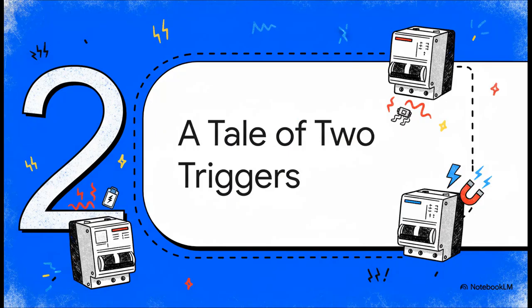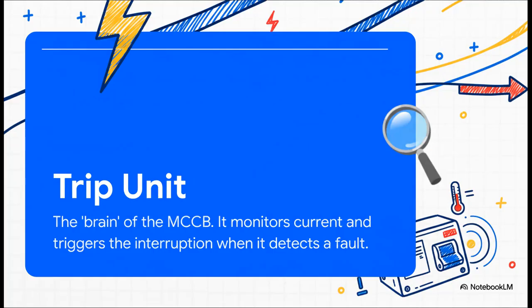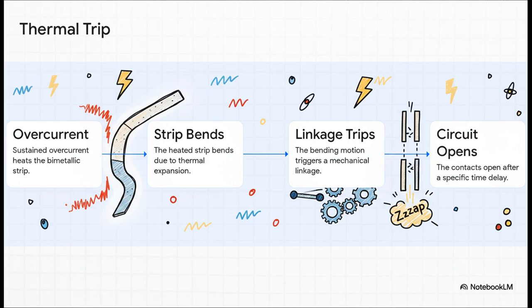Okay, so how does one little box pull off this dual protection mission? Well, it's not with one single mechanism. It's actually a really clever combo of two different systems working together. You could call it a tale of two triggers. But before we get to those triggers, we have to meet the command center, the trip unit. This is the brain of the whole operation. This is the part that's constantly sensing the electrical current, and when it sees something's wrong, it's the one that yells, "Shut it down." For that slow burn overload problem, the MCCB uses what's called a thermal trip.